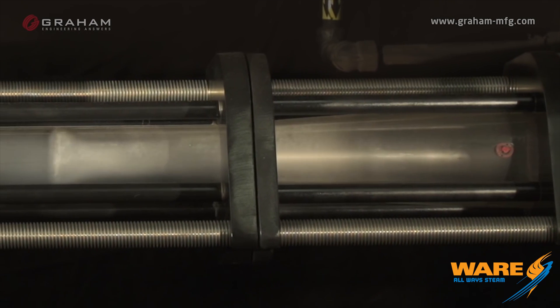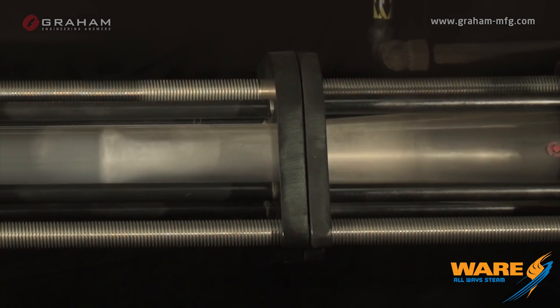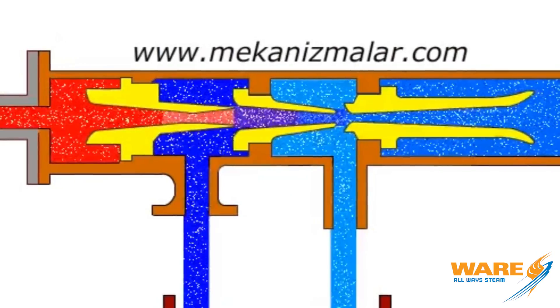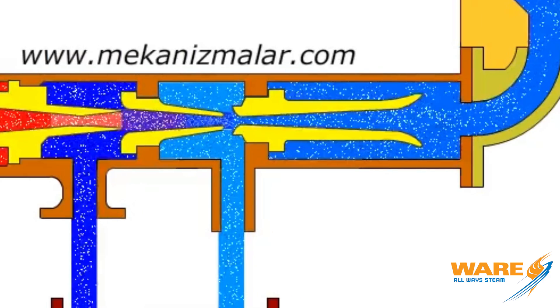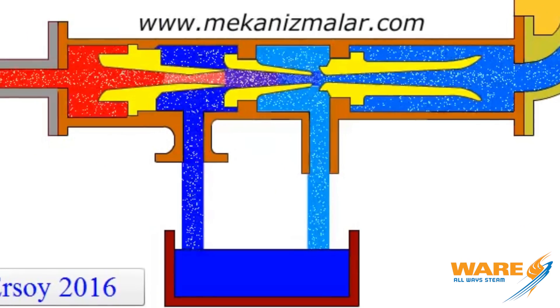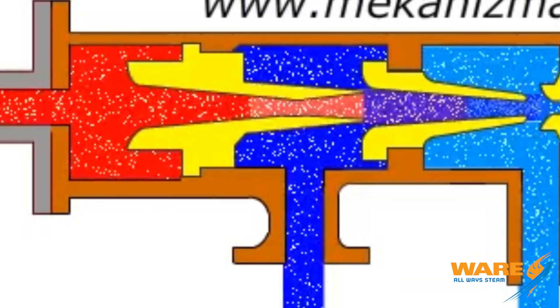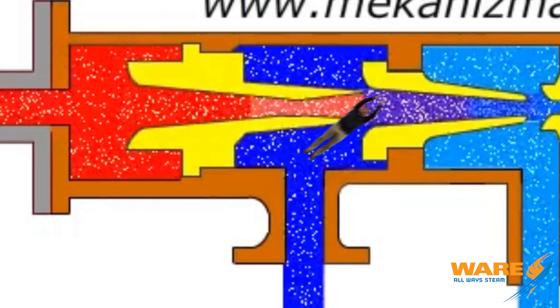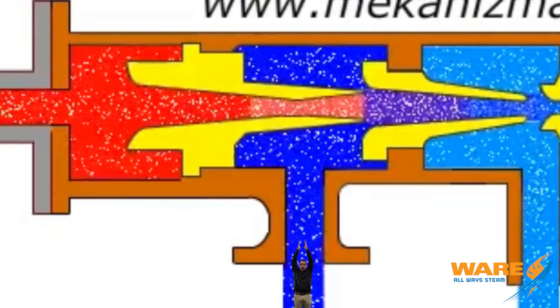In fact it's going to become supersonic — this is the best part of the injector right here. The speed of that steam coming through the nozzle is going to reduce the pressure at the end of the nozzle, so much so that it's going to reduce it below atmospheric pressure. If you look below we see a water supply coming in, and when that pressure around the nozzle gets reduced it's going to create a vacuum or a void. The water is going to rush in to fill that void and mix with that high pressure steam.